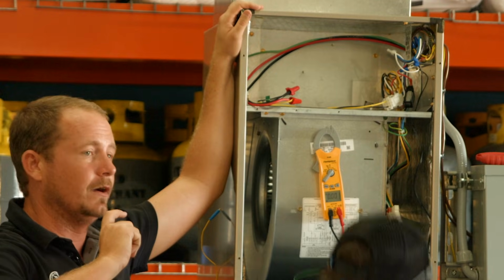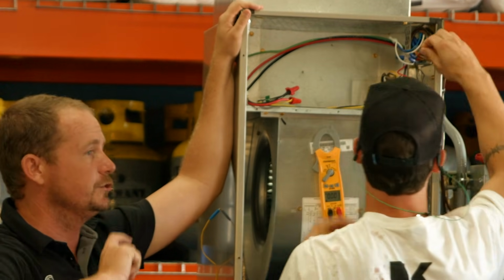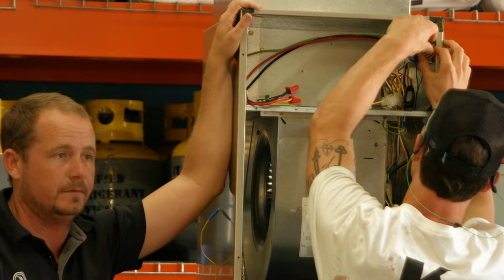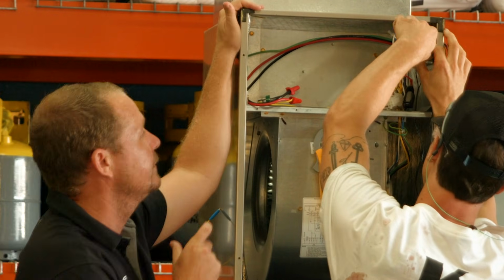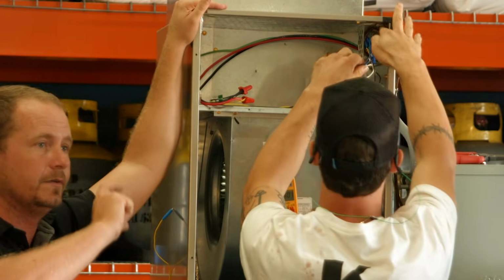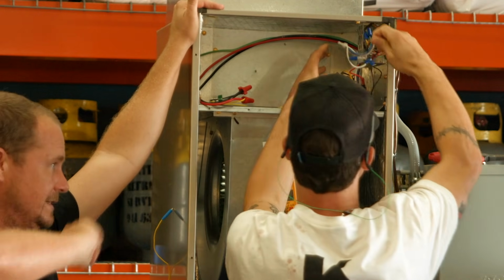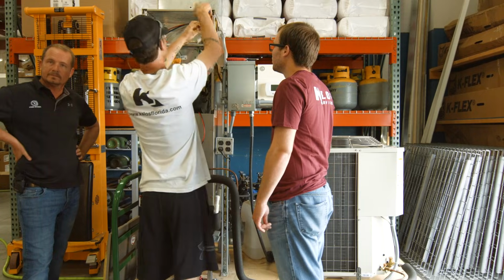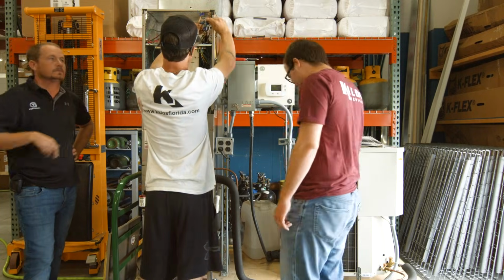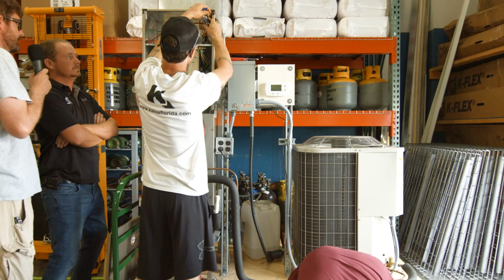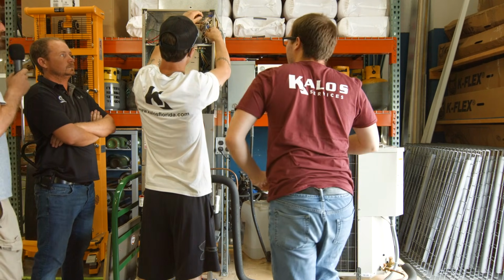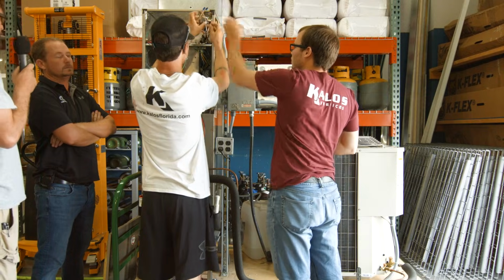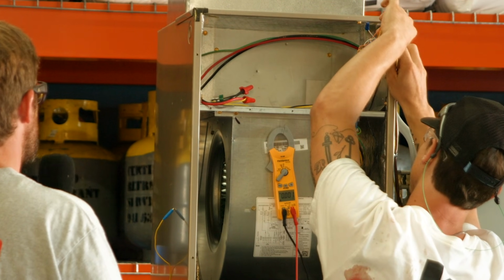It could be shorted to ground, but it could also be shorted to the other side of the circuit, which is common, which electrically on this unit is the same as ground, because the common is dedicated to ground. It's actually grounded on the common side. So just another way to approach it, I would unplug the low voltage wires from the transformer and just start sticking meter leads into wire nuts to find the circuit that's shorted to either common or ground.